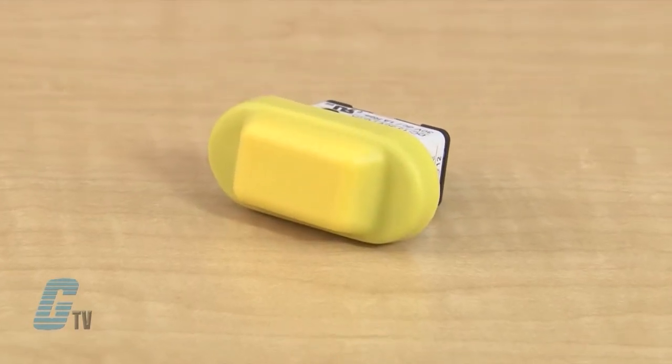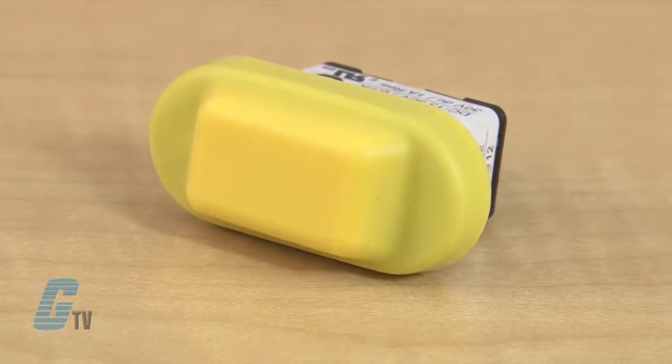The monitoring switches monitor the off status of the three position enabling switch, whether the button is returned to position 1 or if the button is pressed to position 3. Two contacts are provided in a 3 position enabling switch so that even if one contact fails, the other contact will still disable machine operation.